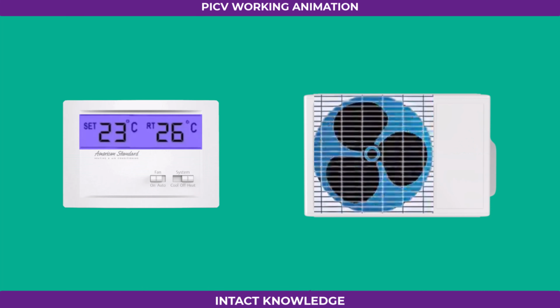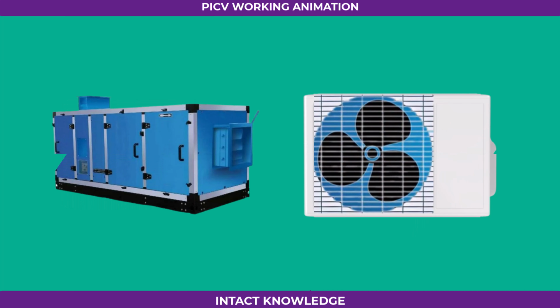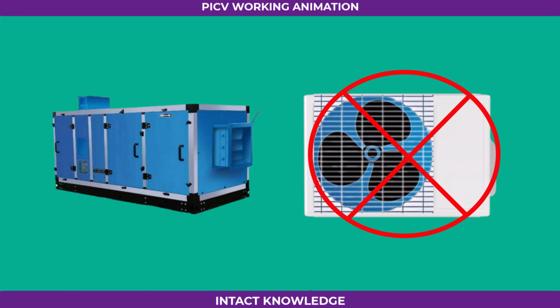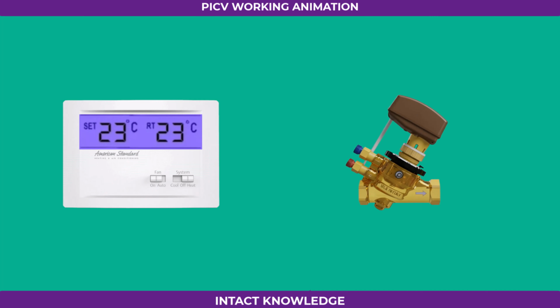In a regular split air conditioner, the outdoor unit automatically shuts off once the room reaches its set temperature. When the room warms up again, the outdoor unit switches back on. But in an air handling unit, or AHU, there's no outdoor unit. It functions as the indoor unit of a central system. So when the room temperature hits the desired set point, the PICV takes over and acts just like that outdoor unit, regulating the flow.